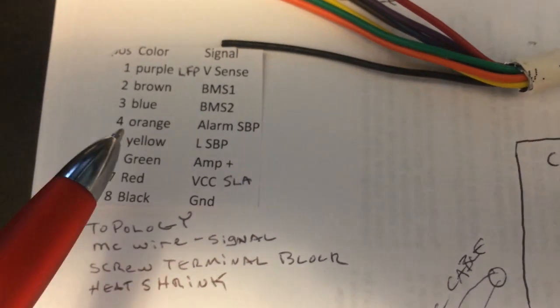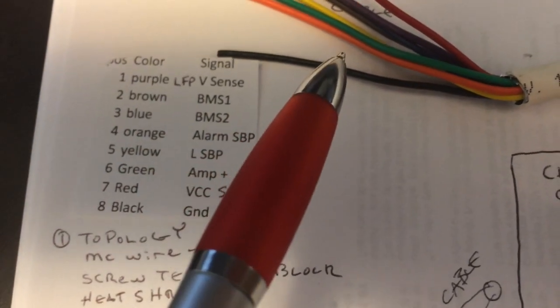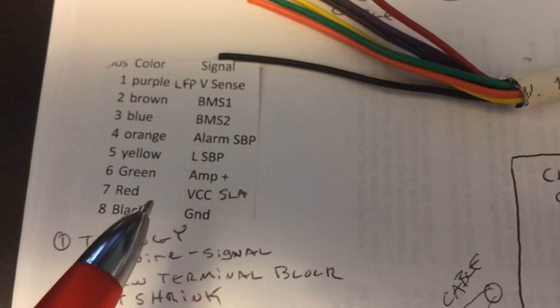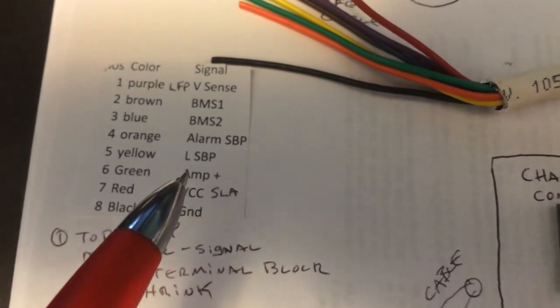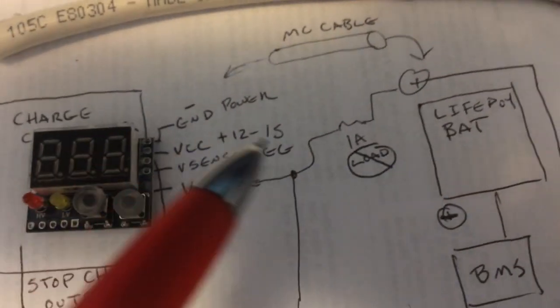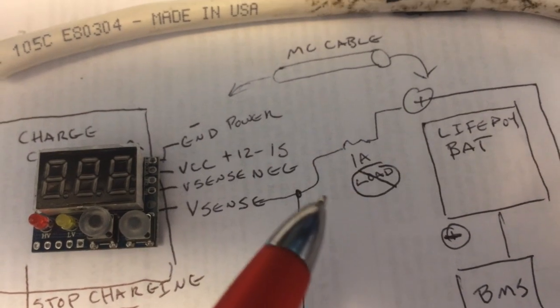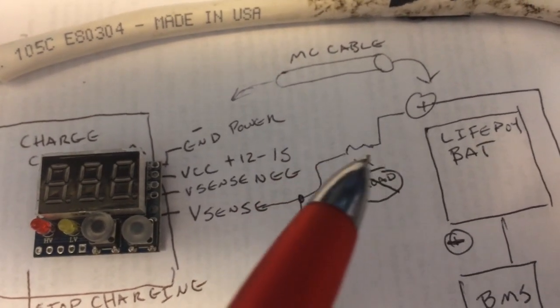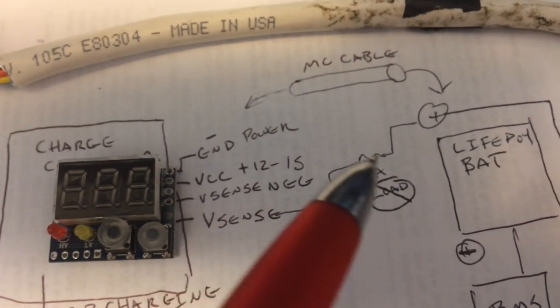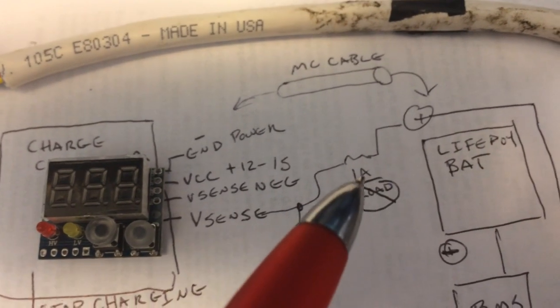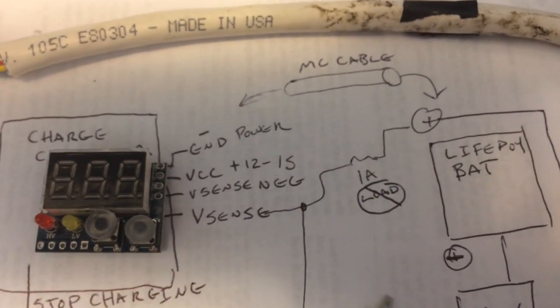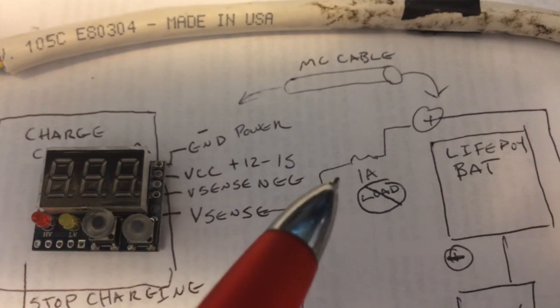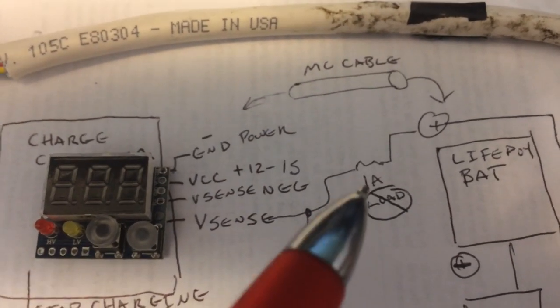So it's just a real easy way. This is 20 gauge, you can put a limited amount of power on it, and I just want to mention one other thing: the voltage sense wire, don't have any loads on this wire. Come right off the battery terminal. You can protect it with 1 amp, but don't put any loads on it. Use it only to sense the voltage.